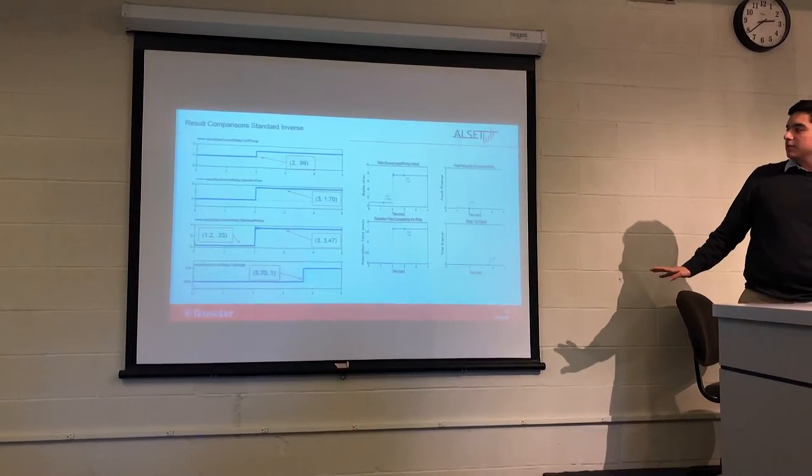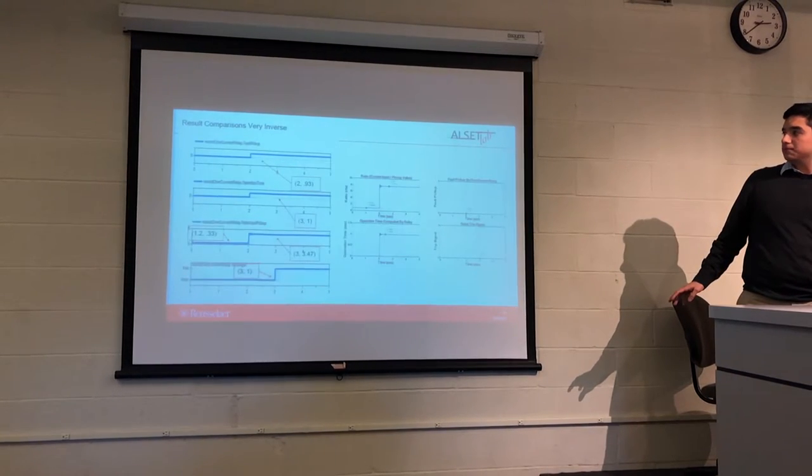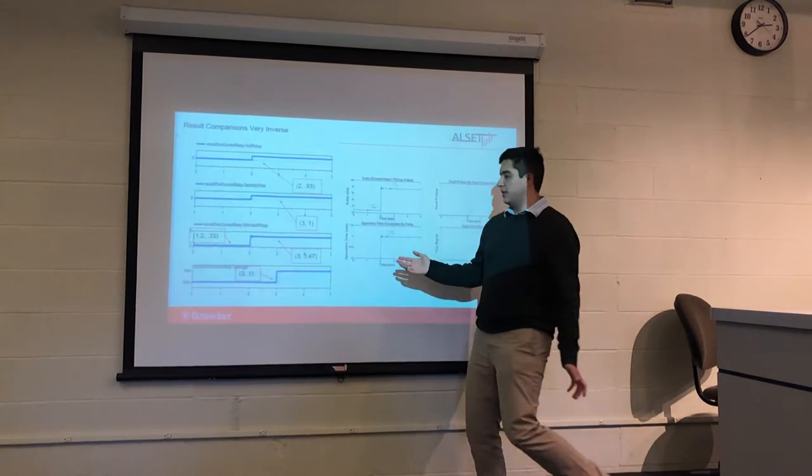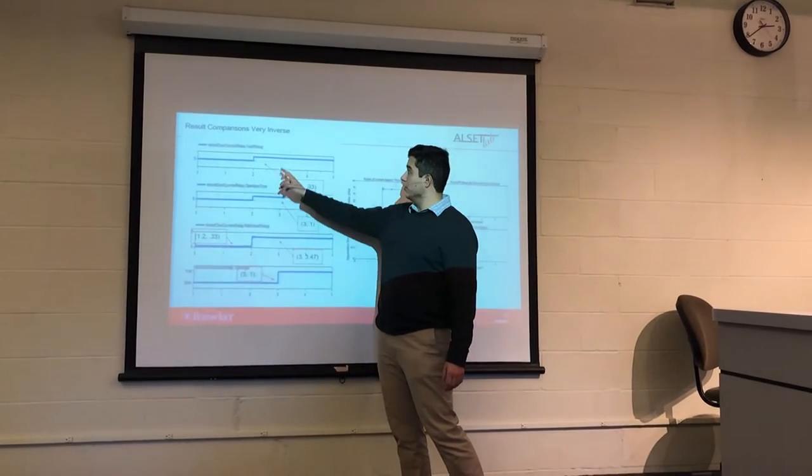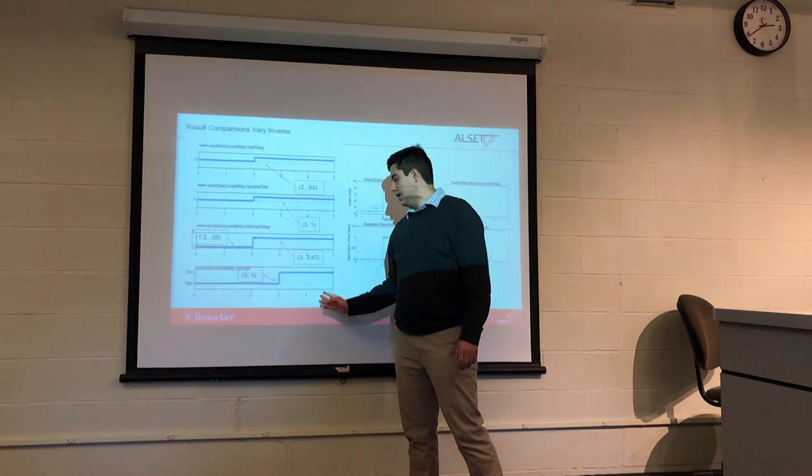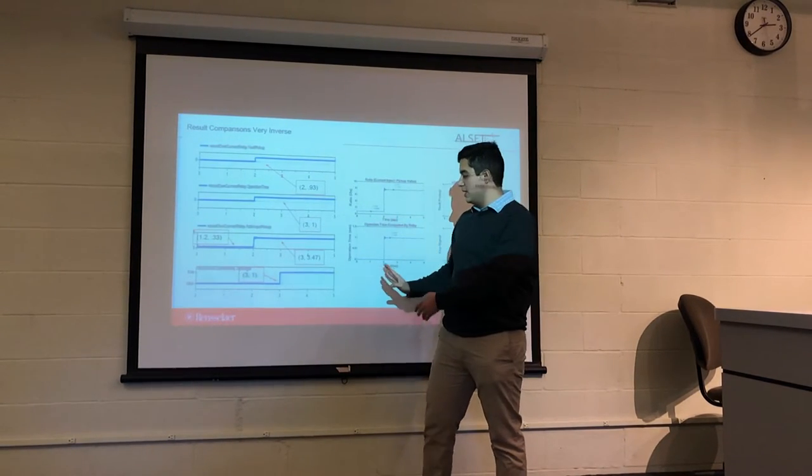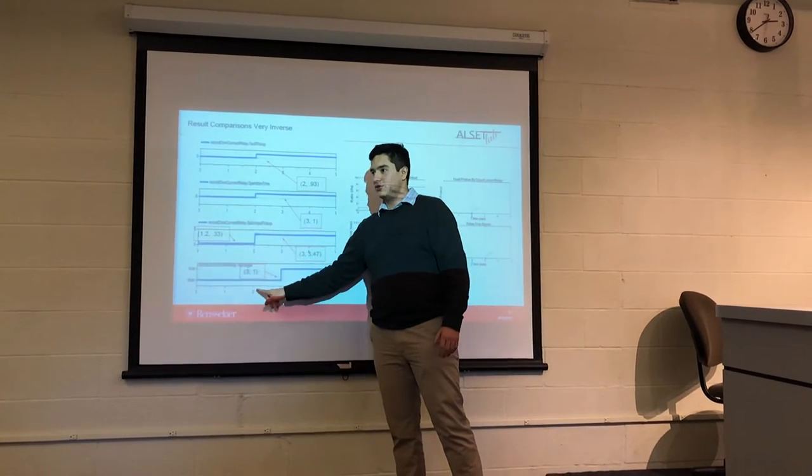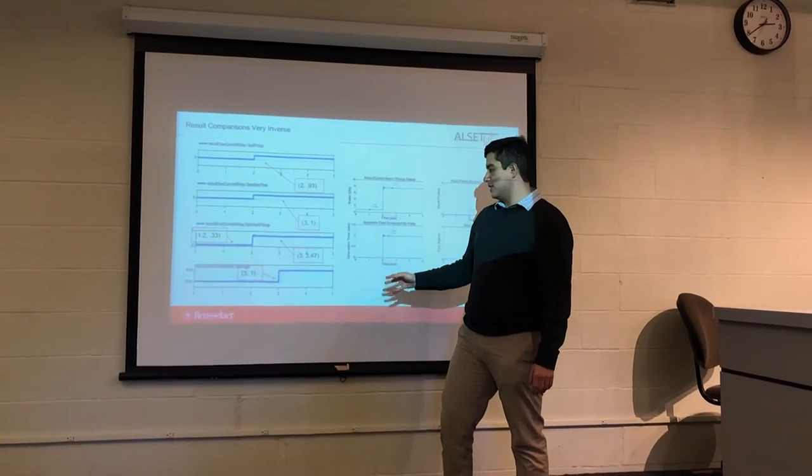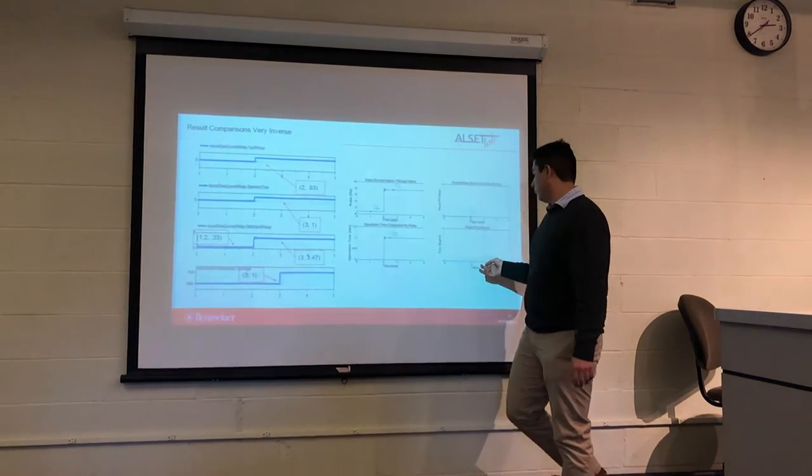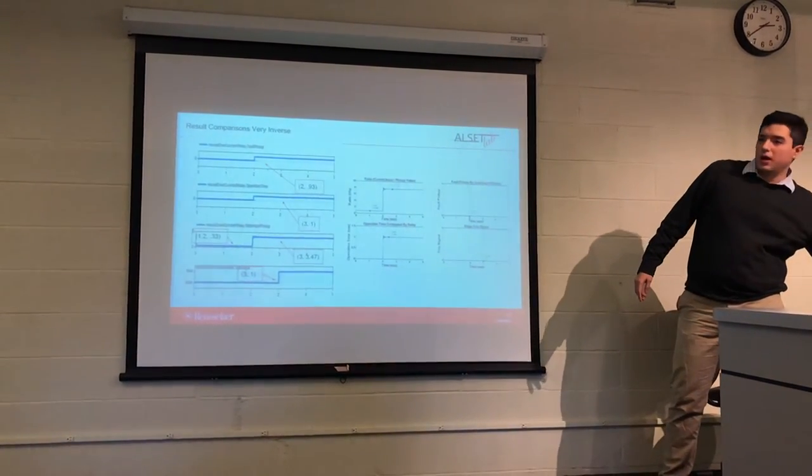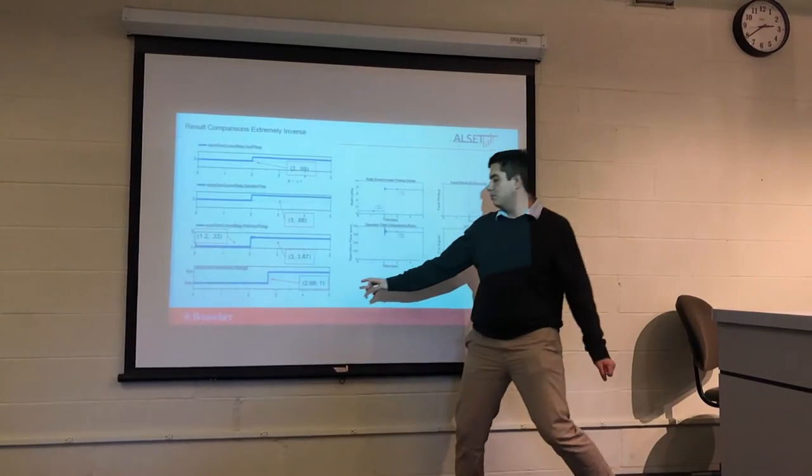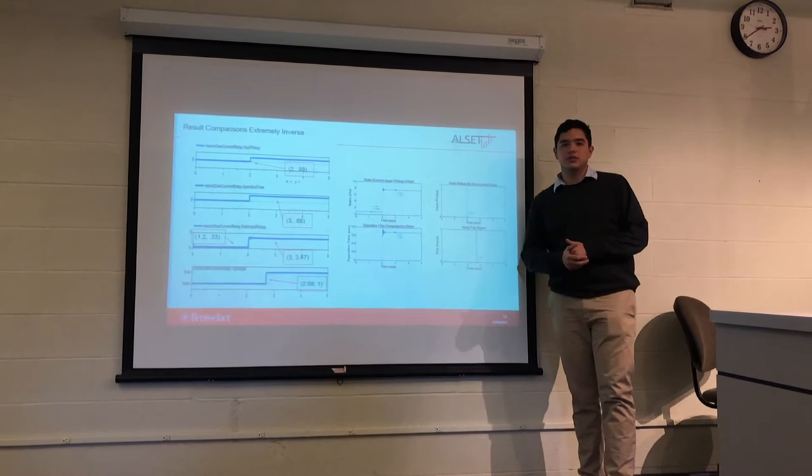This happens the same for all of the different types of relays. So, for example, in here, for the very inverse, we have a 3.1. We go from standard, very inverse, to extremely inverse, and the trip time, depending on the alpha and the C, starts going closer to whenever the fault actually happened. In this case, it goes to 3. Here, it's 2.99. And then lastly, the extremely, which ends up being 2.68, and then here, it's also like 2.67.